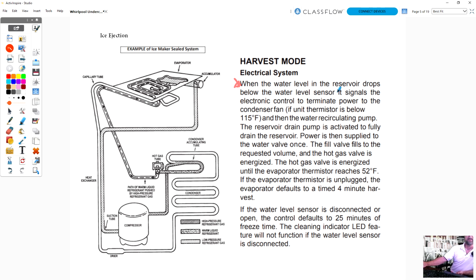But they would just run it for a certain amount of time to fill up with water. Now they have something like a float switch, or actually it's not a float switch. It's a unit that's in the water, and it runs a low voltage current through the water. And once the water reaches a certain level, the board knows how much water is in there. So the cycle of the ice maker is actually done by the water level control. So if we look here, below the water level signals the electronic control to terminate the power to the condenser fan. So once the water level gets to a certain level, there's a thermistor that, if the temperature's over 115 degrees, the condenser fan's going to run. If it's lower, then they're not going to turn on, especially if someone has it in a garage or a basement where there's colder weather.